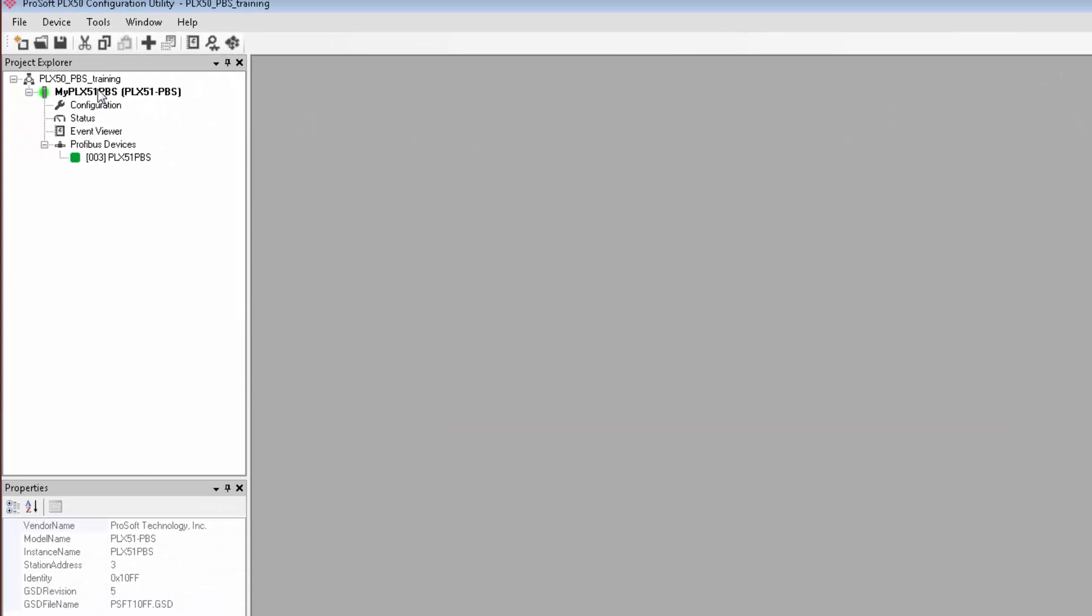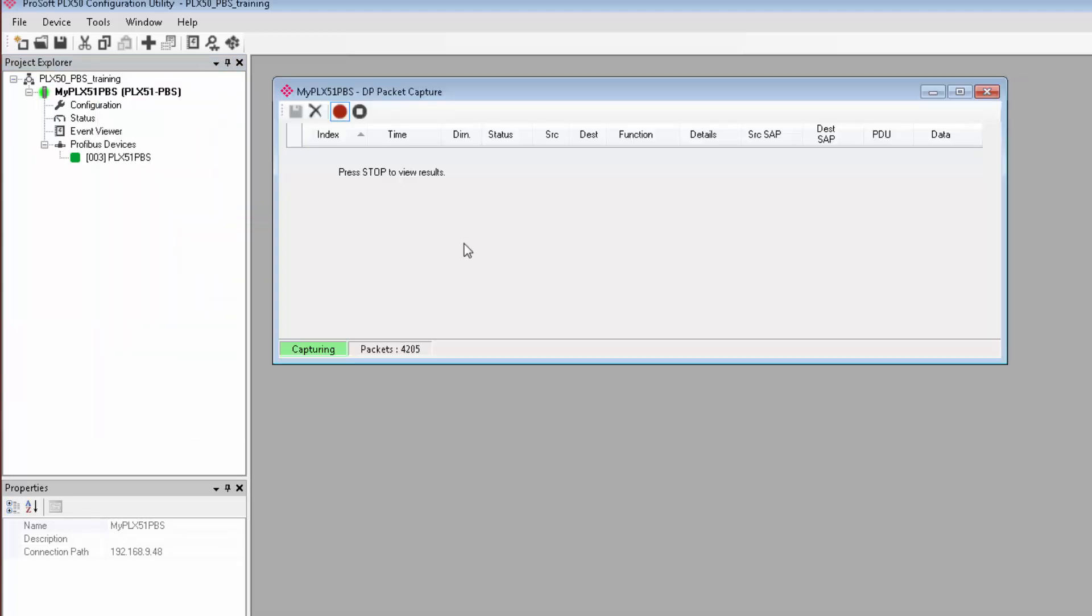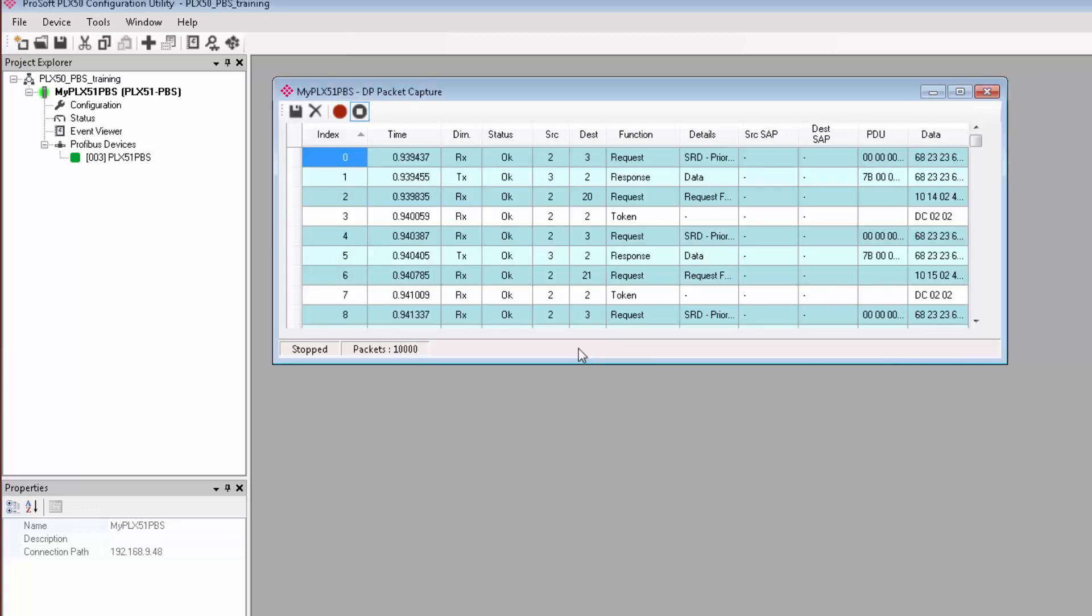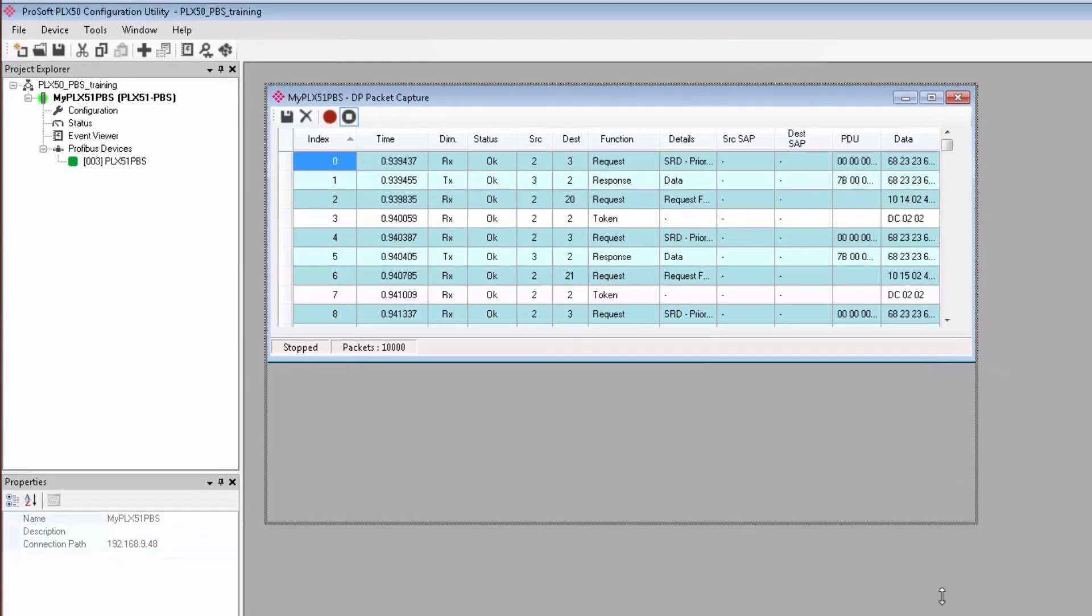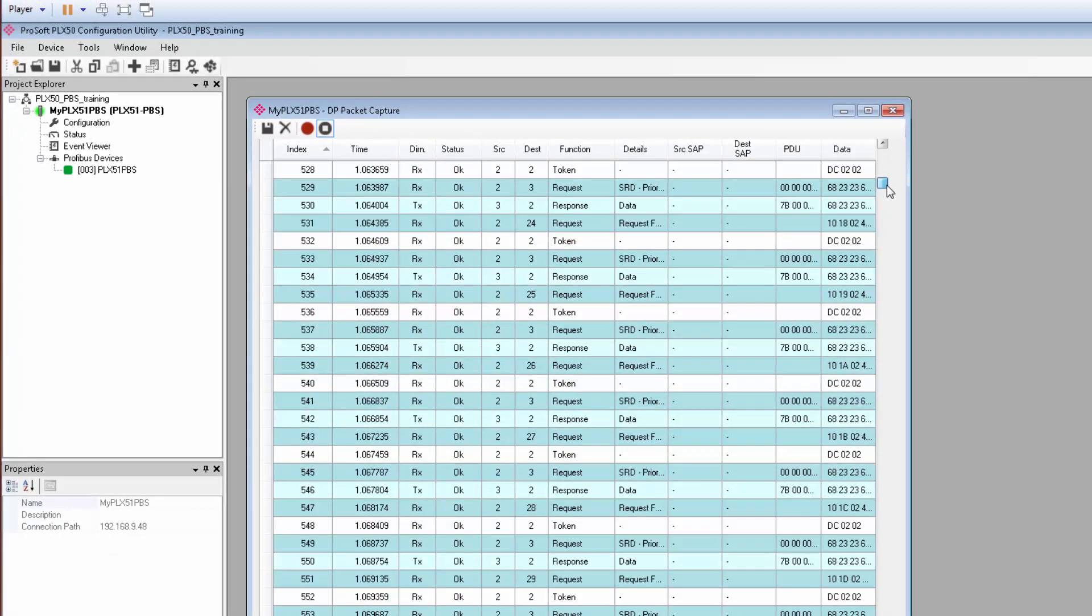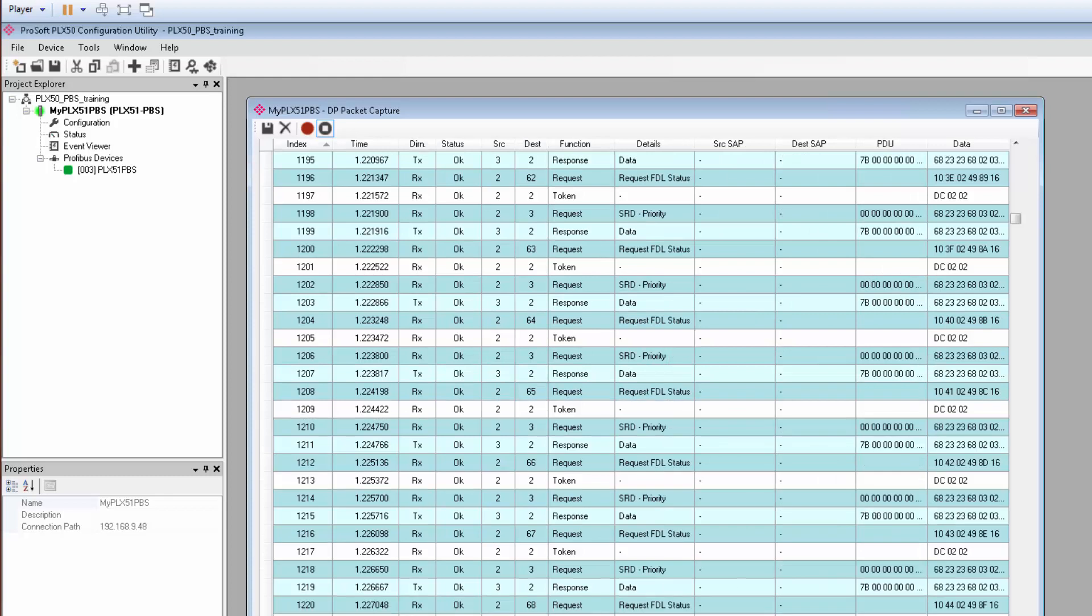Also, if we right-click on the PLX51 in the Project Tree view, we can select the DP Packet Capture Utility. This opens the Packet Capture window, and the PLX51 will automatically start capturing all PROFIBUS packets, and will continue doing so until you press the Stop button, or once it's captured 10,000 packets. Once the capture process is stopped, the data is presented in a table like this. All the packets are displayed in the order that they were captured, and you can see the time is here in microseconds. We also have the direction, either transmit or receive, the packet status, the source and the destination of the packet, the function, and finally, the raw data over on the right side here. You can save these captures by clicking the disk icon up in the toolbar.